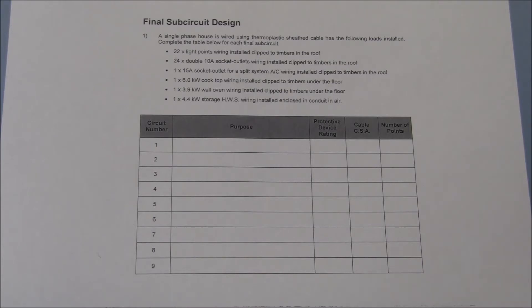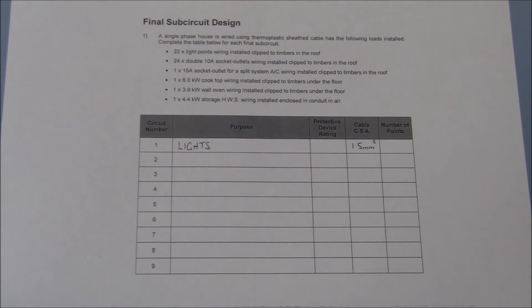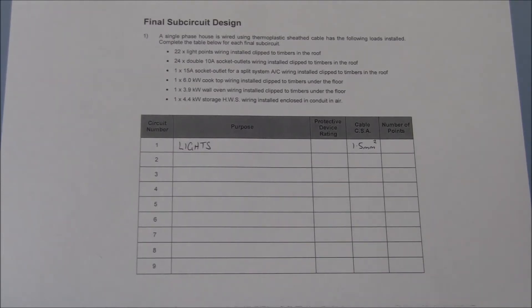Let's begin with the 22 light points. Circuit number one will be a light circuit. The cross sectional area for the cable I've decided to use is 1.5mm squared. You could use 1mm squared cable for a lighting circuit, however I've decided to go with 1.5mm squared. Now that we've determined our cable size, we need to work out what size protective device rating we'll have. For this, we're going to refer to table C6.